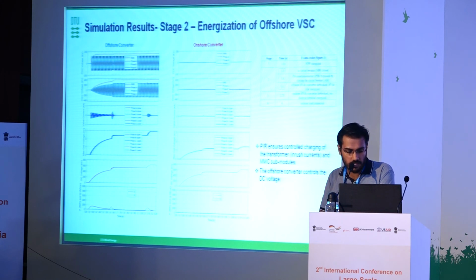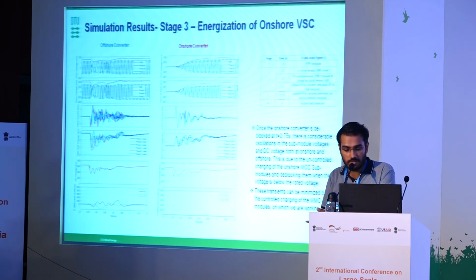These are the initial results. You can see that the PIR helps control the charging inrush currents, and in the offshore converter submodules there is a transient, but then when the submodule capacitors are charged, the HVDC link is controlled. When the onshore converter is deblocked, there are, as you can see, very considerable oscillations in the voltages of the submodule capacitors of the onshore converter. This is because the offshore MMC submodule capacitor energy is used to energize the onshore MMC submodule capacitors, and this can be done in a controlled way.